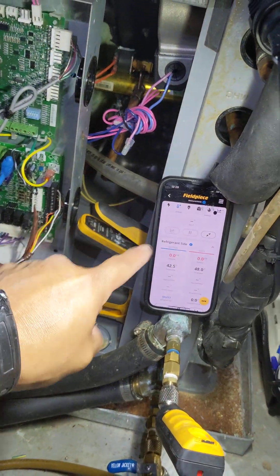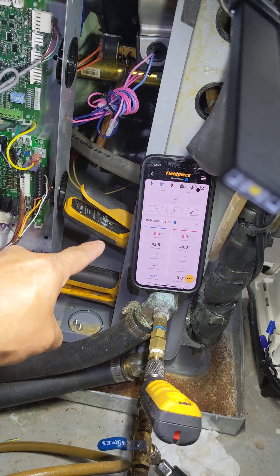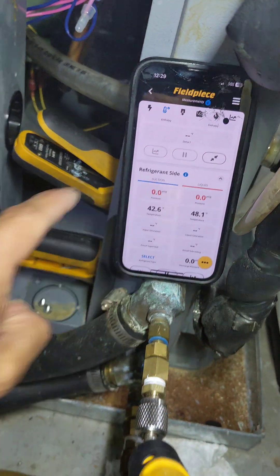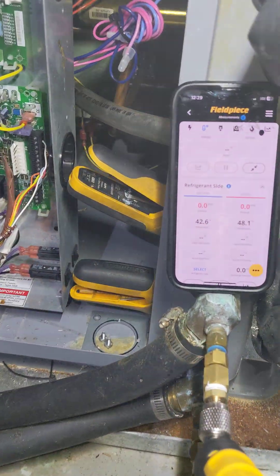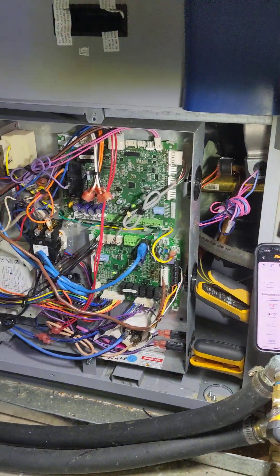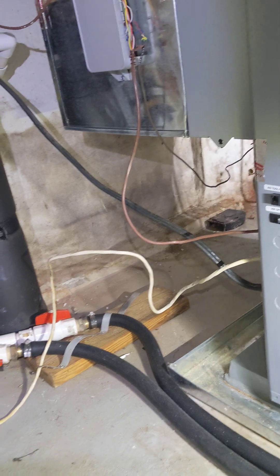So this is the actual water pressure on these geothermal loops — zero. When the system was running, I was getting four and six PSI; the circulator pumps were creating some pressure. But we need more water pressure. The question is: yes, it's leaking water, but it would be a big repair.